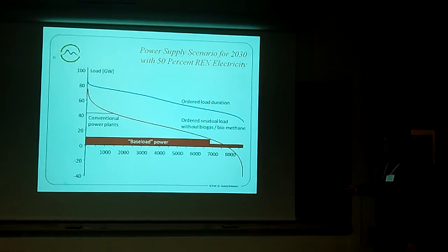And these lignite power stations have about 6,500 operation hours. Plus, you cannot shut down at zero because you must still have them on stream for technical reasons, for regulation power, and also because you may have to start them up very fast. So, of course, no lignite power station will run all year. There are always 1 or 2 months where they are in revision. But this means this is baseload power. Seen from a CO2 point of view, this would be a very CO2-emitting system.